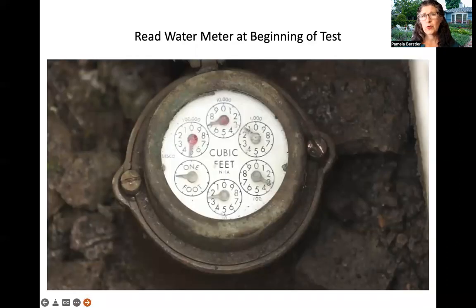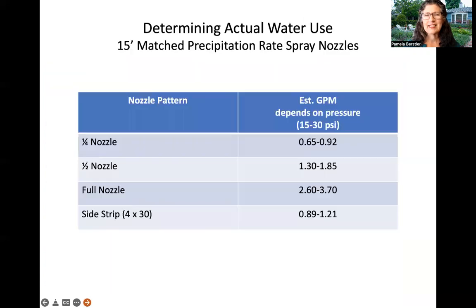And then the other thing that you're going to want to do is read the water meter before you start the test. This whole process is a whole lot easier if there's more than one person, but if not, you're doing a little bit of running back and forth. Now, sometimes that water meter is not accessible. And the reason we look at the water meter is that it's going to help us figure out how much water actually was distributed during our irrigation audit. But if that's not possible, there are calculations that you can do that get you pretty darn close.